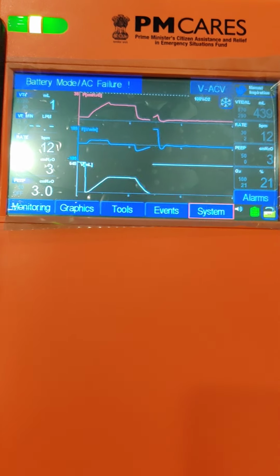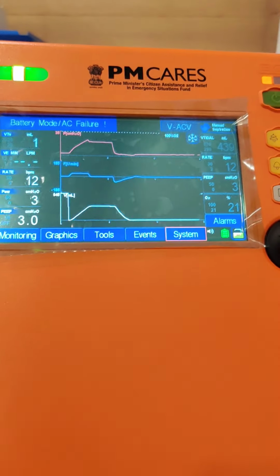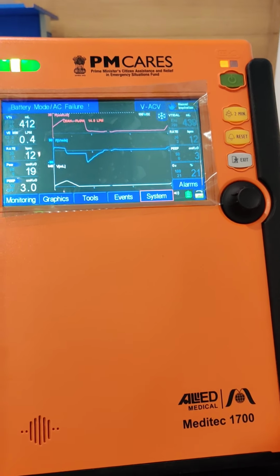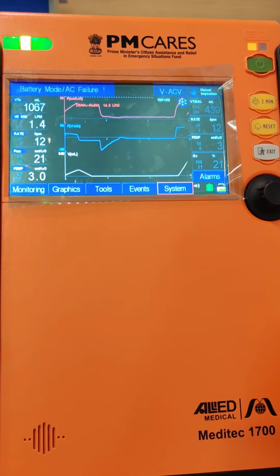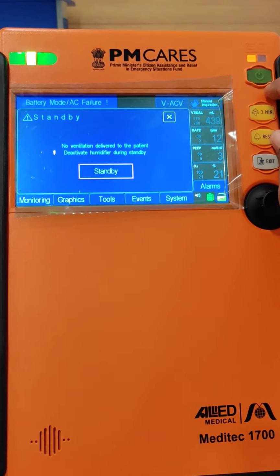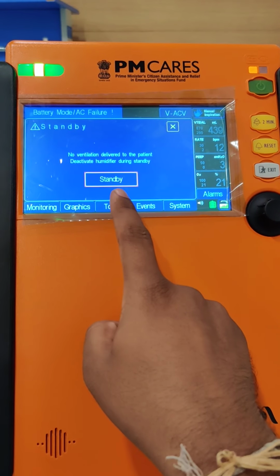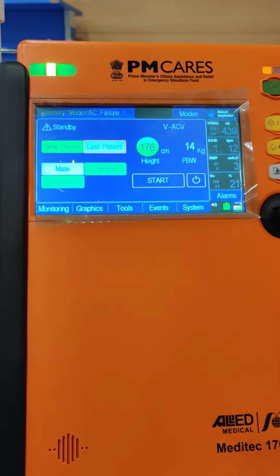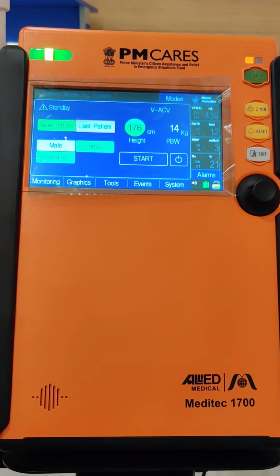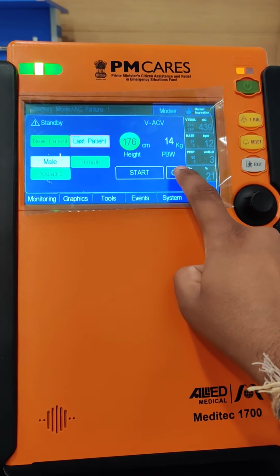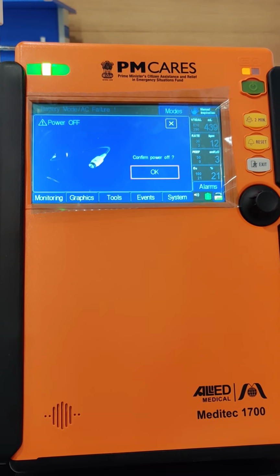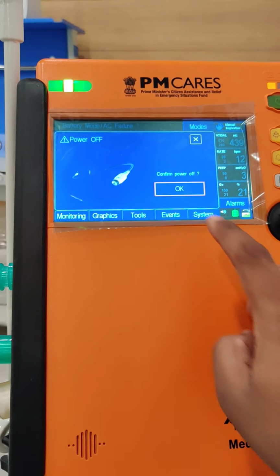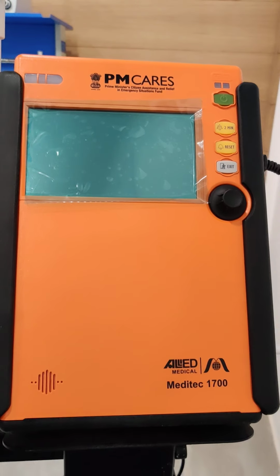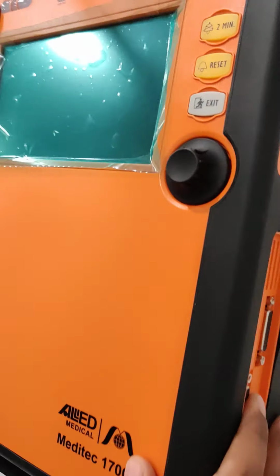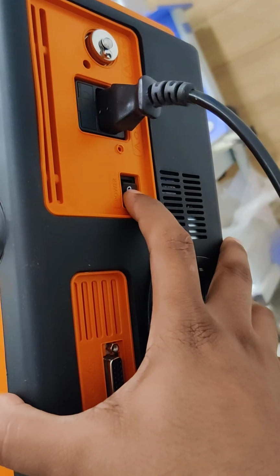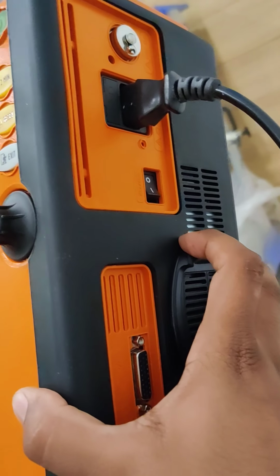Now at the end of this video, I'll be discussing the only thing left, which is how to turn off this ventilator. Right now the ventilator is running. To put this ventilator in standby, you have to press this green button over here. Then you will get this standby confirmation. You have to touch standby. Now your ventilator has gone into the standby mode. Now for turning this ventilator off, there is an off indication which comes over here. You have to press this, and for confirming you have to press the OK button. When you get the beep sound, on the side you have this on-off switch. You have to move this on-off switch to the 0 position. Now your ventilator is turned off.